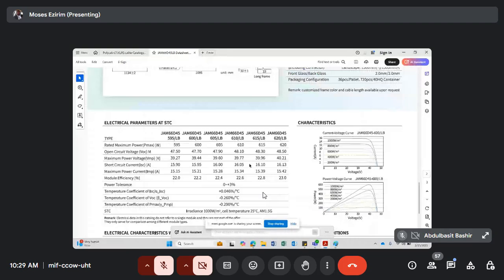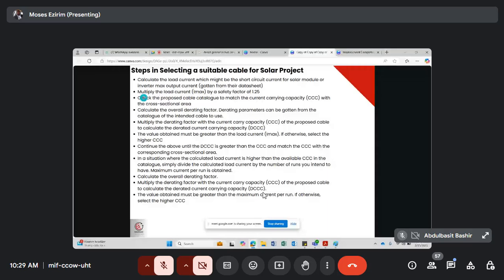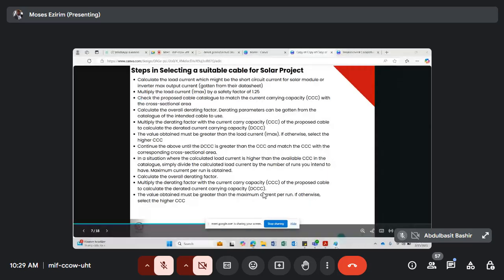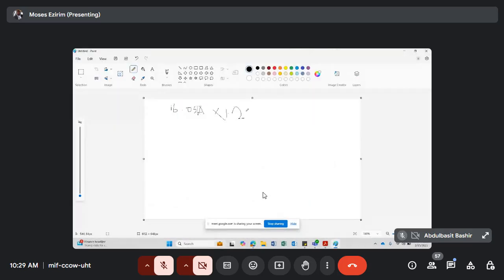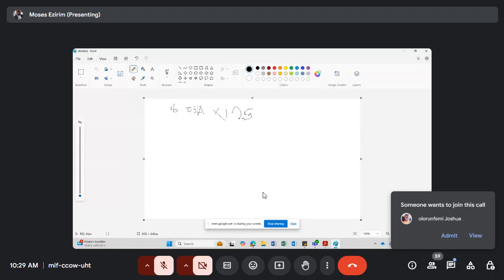Now, if you are doing load currents, which is 16.05, times 1.25 - now you might not multiply. Do you know the reason why I'm saying you might not multiply? Because it is already the short circuit current, and that is the maximum current that can actually flow. Even if positive and negative should mistakenly touch each other, the maximum current that can flow is 16.05. So if you feel like multiplying by 1.25, you can go ahead. If you don't want to multiply, you are still on the good side.